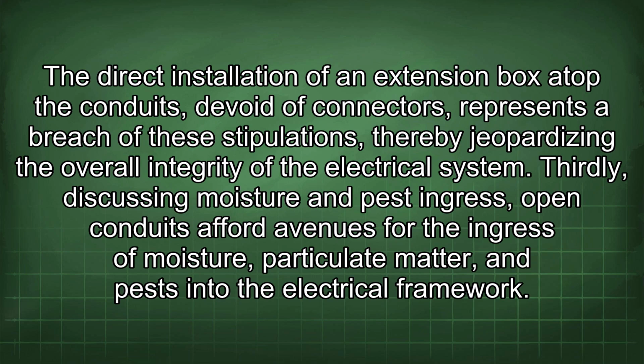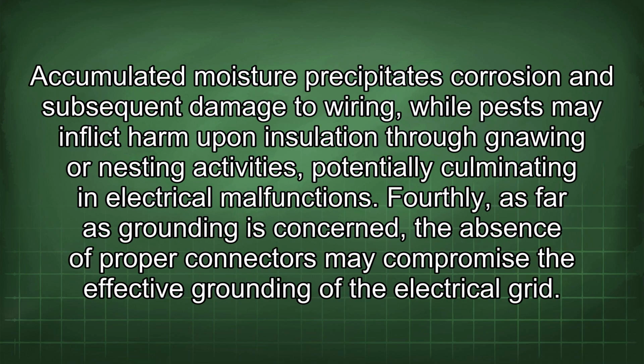Thirdly, discussing moisture and pest ingress. Open conduits afford avenues for the ingress of moisture, particulate matter, and pests into the electrical framework. Accumulated moisture precipitates corrosion and subsequent damage to wiring, while pests may inflict harm upon the insulation through gnawing or nesting activities, potentially culminating in electrical malfunctions.